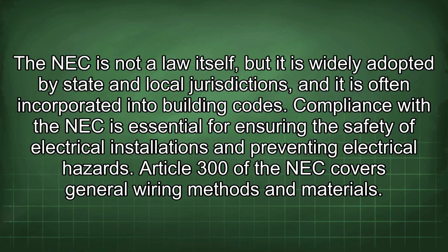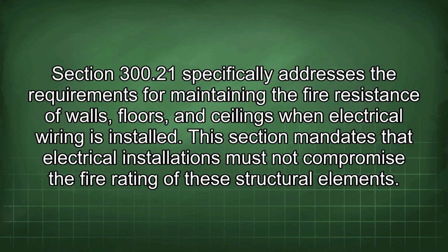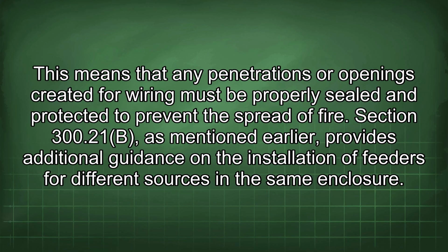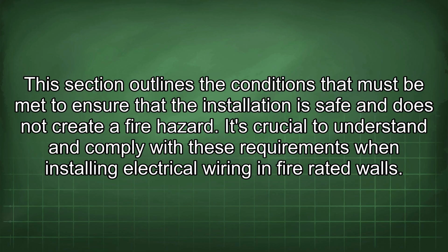Article 300 of the NEC covers general wiring methods and materials. Section 300.21 specifically addresses the requirements for maintaining the fire resistance of walls, floors, and ceilings when electrical wiring is installed. This section mandates that electrical installations must not compromise the fire rating of these structural elements. This means that any penetrations or openings created for wiring must be properly sealed and protected to prevent the spread of fire. Section 300.21(B), as mentioned earlier, provides additional guidance on the installation of feeders for different sources in the same enclosure. This section outlines the conditions that must be met to ensure that the installation is safe and does not create a fire hazard. It's crucial to understand and comply with these requirements when installing electrical wiring in fire-rated walls.